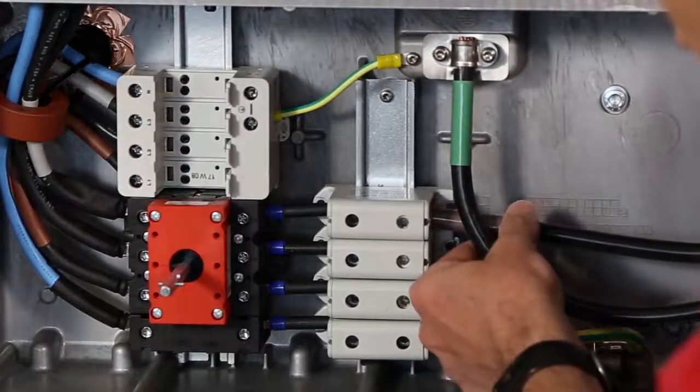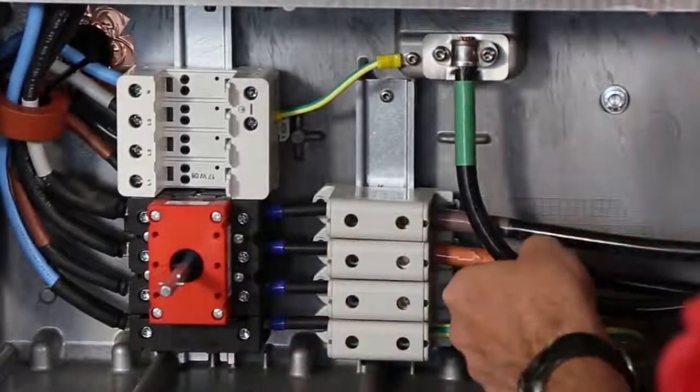Next we release the screws on the AC connection block with the Torx 30 screwdriver, bring in the conductors to the lower AC connection opening, and insert them on each of the three connection points. Tighten them down with the Torx 30 screwdriver.